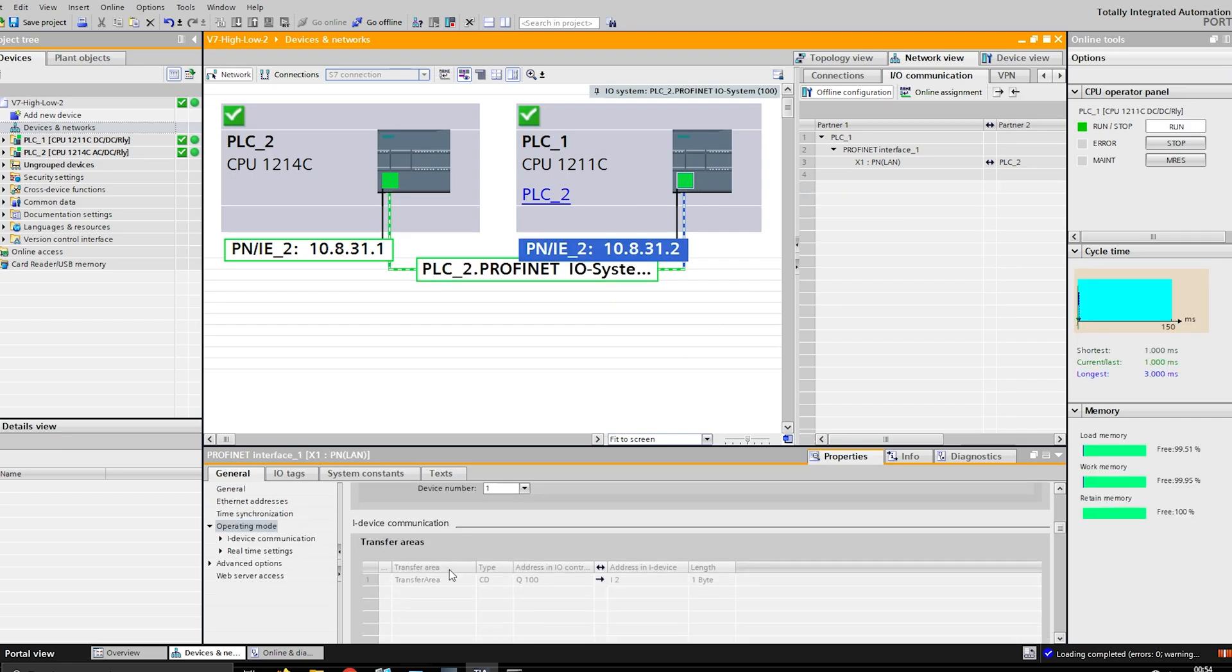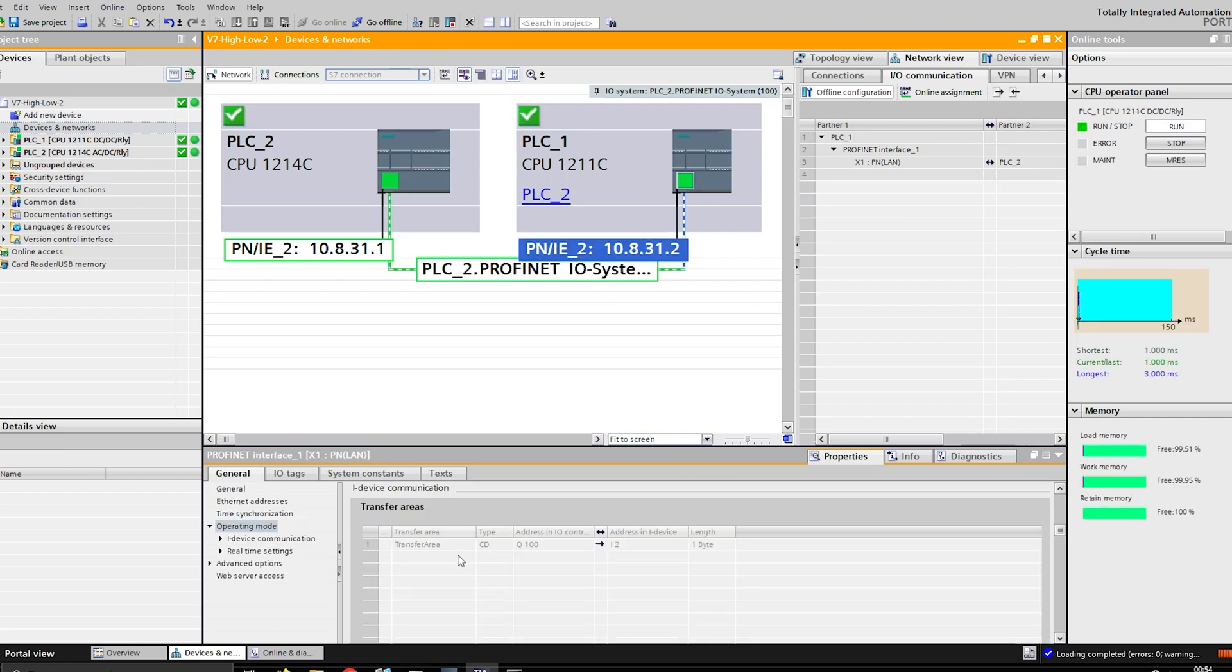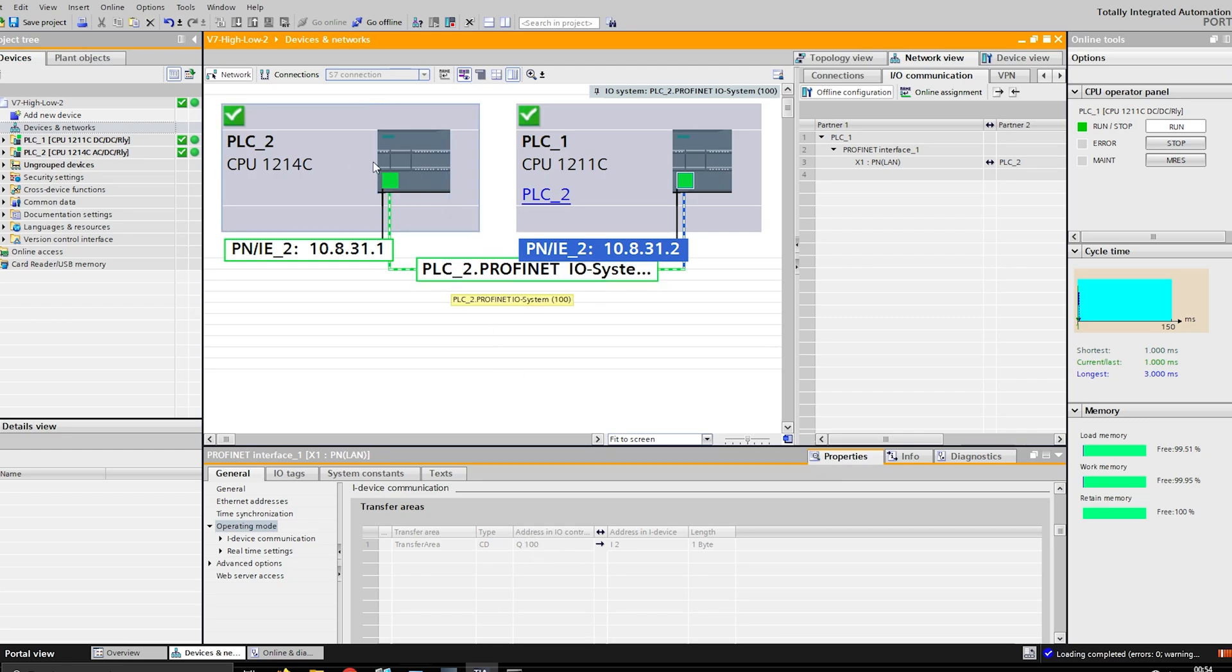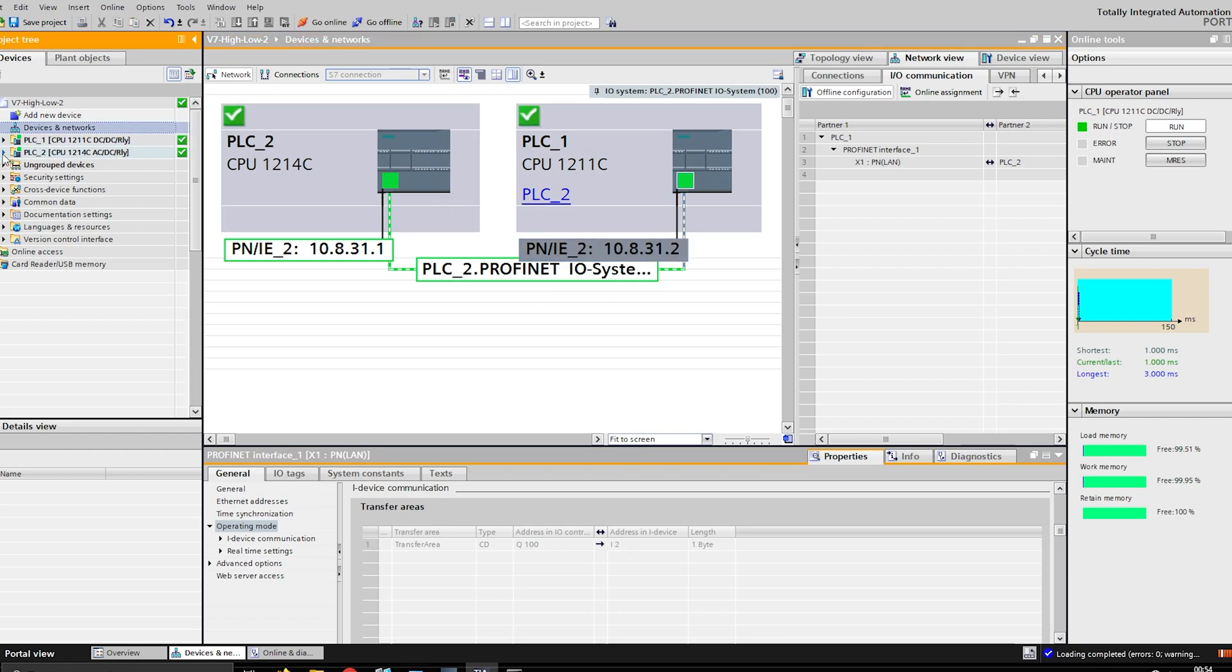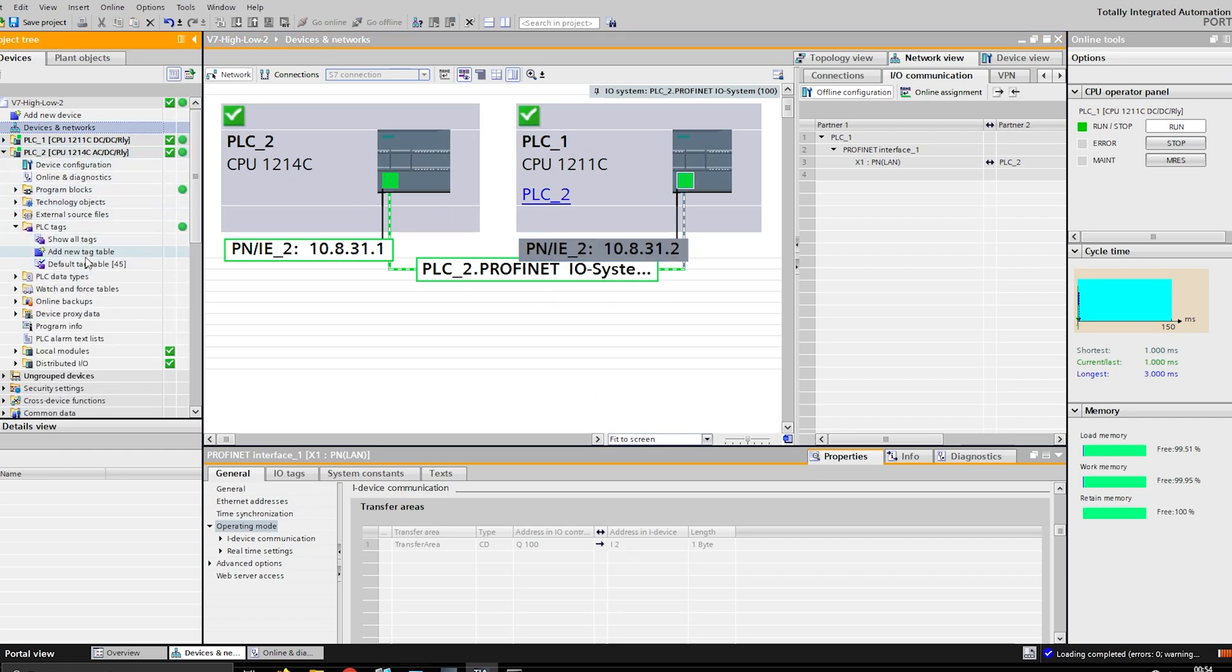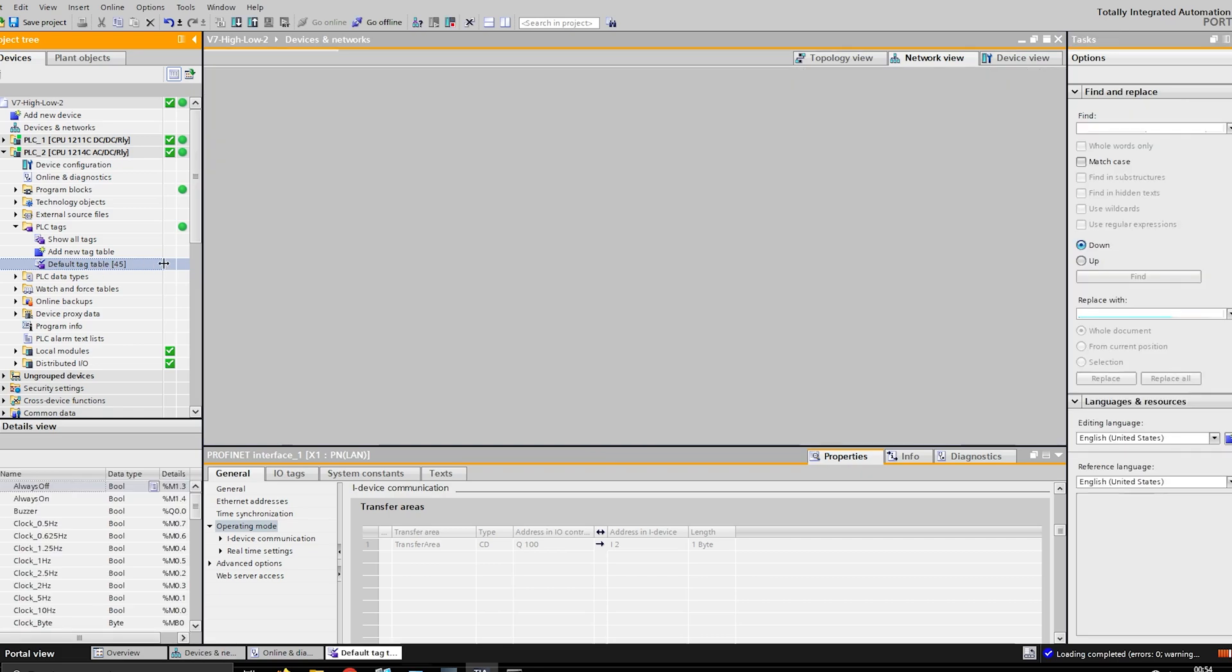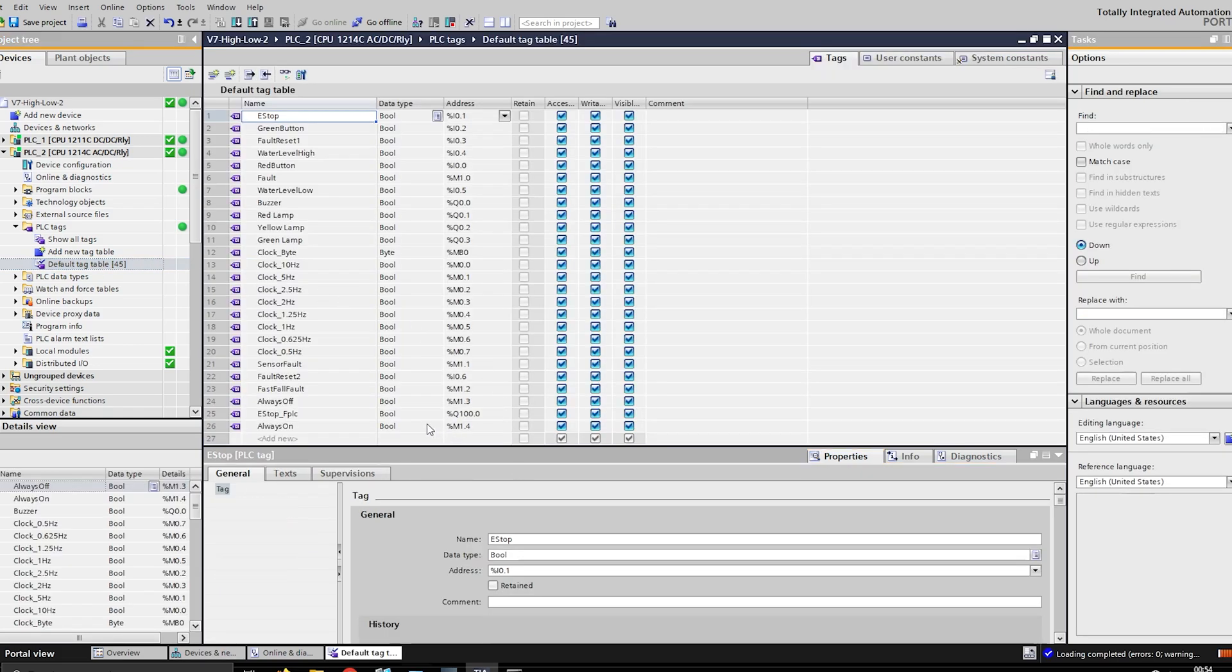The tricky part now is setting up a transfer area. You need to tell it what information it should be transferring. What I've done was I've said okay, take the Q100 output on this PLC here, take it and send it to the I device, which is this device, and send it to input 2.